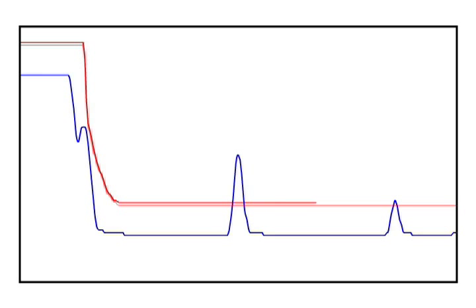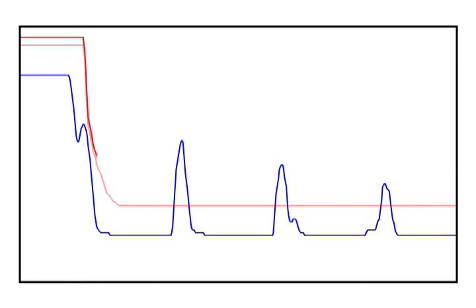We begin to see multiple echoes following the true material echo. The dynamic TVT compensates for these strong multiple echoes by moving further away from the noise floor.